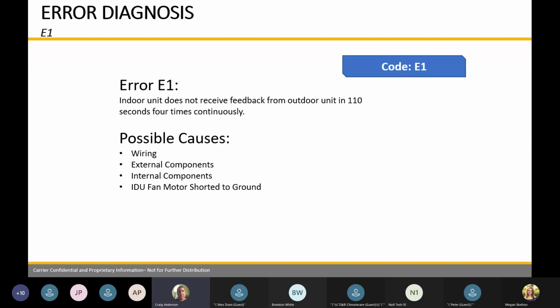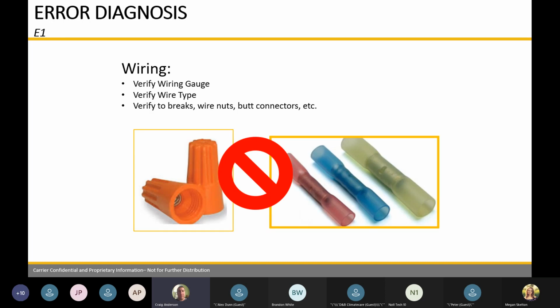E1's our biggest one. Error code, outdoor and indoor unit are not communicating. Wire, like I said, 14 3-stranded wire, indoor to outdoor unit. You don't want marrettes, you don't want junction boxes. L1, L2, S, make sure it's the same indoor, outdoor unit. Component failure, indoor board, outdoor board, stuff like that for E1, but E1's a communication code. So like I said, make sure there's no wire connectors between the wires. We want a solid wire from indoor to outdoor unit.